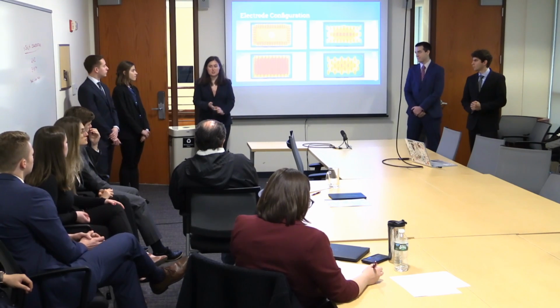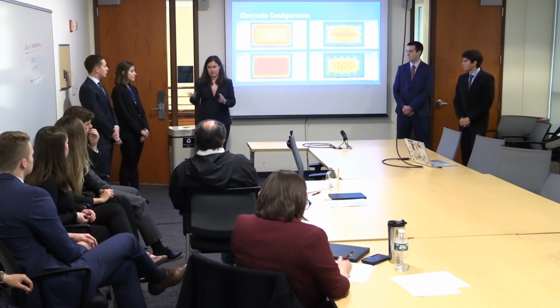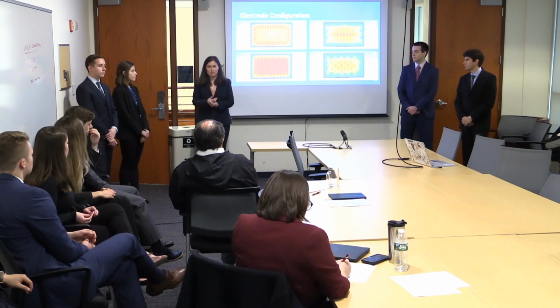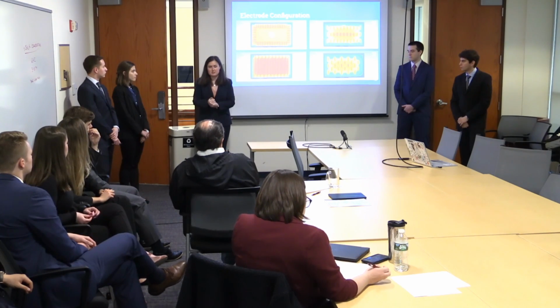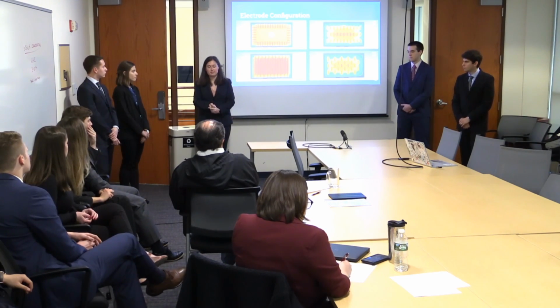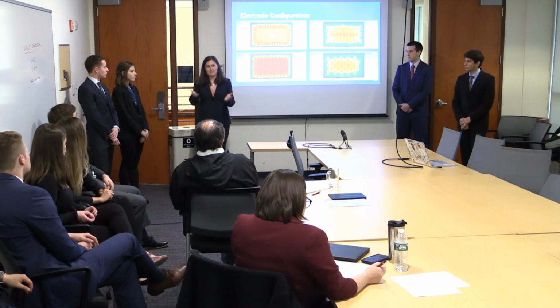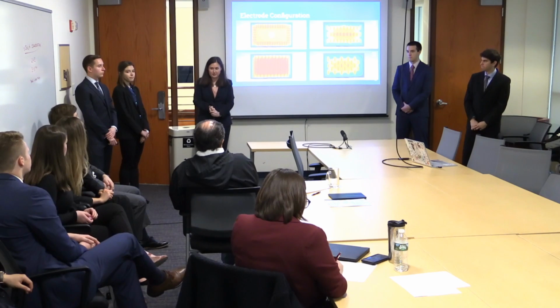Yeah, and that's also why we looked into the cost of it, where we wanted to make sure it didn't cost exorbitantly more, because there isn't a government forcing you to do it right now. So that's why we looked into mitigating the cost if you don't need to use the alum, or other things. Even if you do need to use the alum, overall it's going to increase it by about $100,000 a year, which is pretty negligible, especially because the MWRA, who charges water to Boston, charges about $3,500 per million gallons, and you're producing 12 million gallons a day times 365 days a year. So the amount that it's going to increase is pennies. So that's the two aspects we were looking at with that.